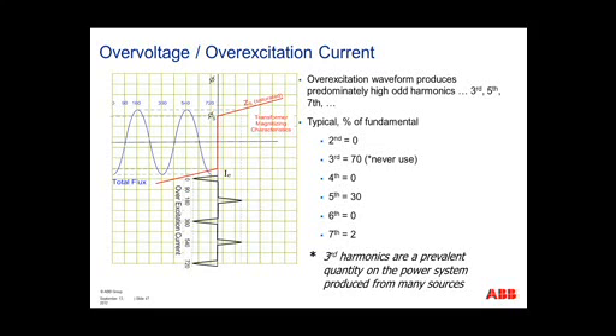Another source of false differential current is when you go into overvoltage or an overexcitation condition. What happens is if you're pushing too much current through the transformer, the core can only output so much, and once you reach that point, you still have a greater current going into the transformer. However, that is not directly proportional to how much current is leaving the transformer. One way to identify this is using third or fifth harmonics. The current going in will represent, when you're in an overvoltage or an overexcitation condition, both third and fifth harmonics.